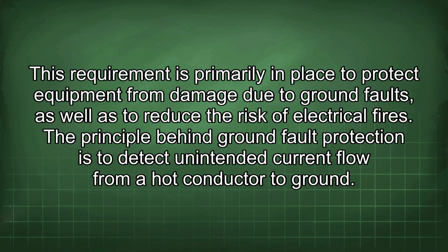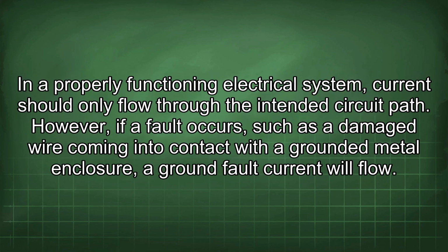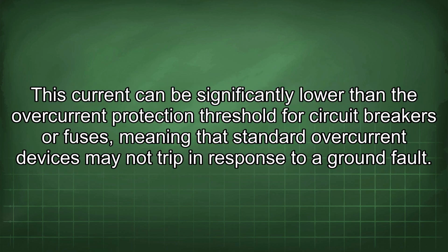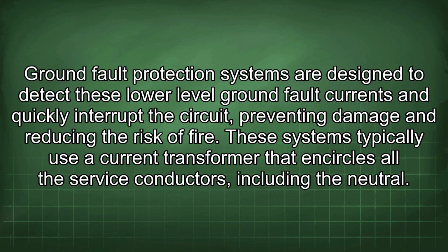The principle behind ground fault protection is to detect unintended current flow from a hot conductor to ground. In a properly functioning electrical system, current should only flow through the intended circuit path. However, if a fault occurs, such as a damaged wire coming into contact with a grounded metal enclosure, a ground fault current will flow. This current can be significantly lower than the overcurrent protection threshold for circuit breakers or fuses, meaning that standard overcurrent devices may not trip in response to a ground fault. Ground fault protection systems are designed to detect these lower-level ground fault currents and quickly interrupt the circuit, preventing damage and reducing the risk of fire.